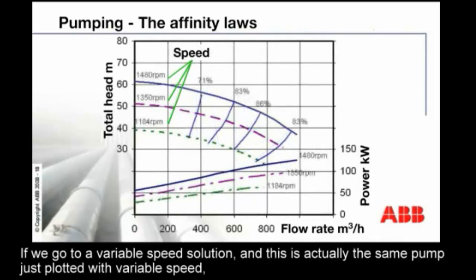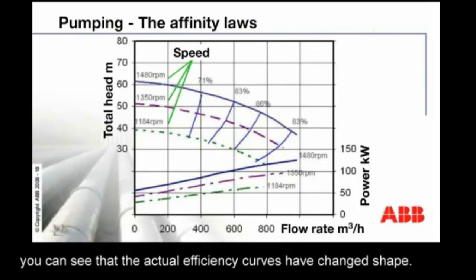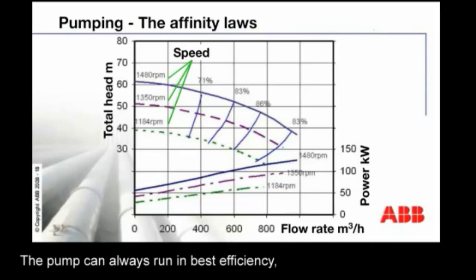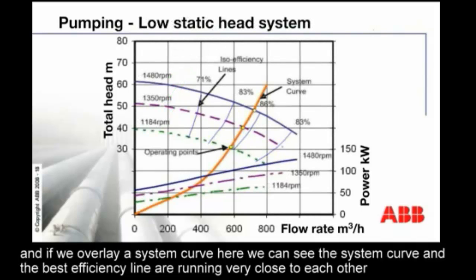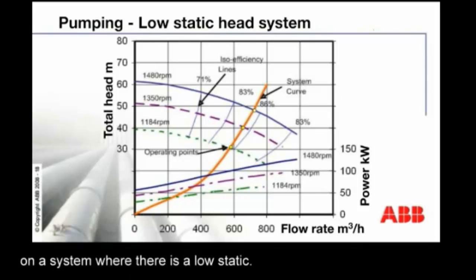If we go to a variable speed solution — and this is actually the same pump just plotted with variable speed — you can see that the actual efficiency curves have changed shape. The pump can always run at best efficiency. And if we overlay a system curve here, we can see the system curve and the best efficiency line are running very close to each other on a system where there is a low static head.